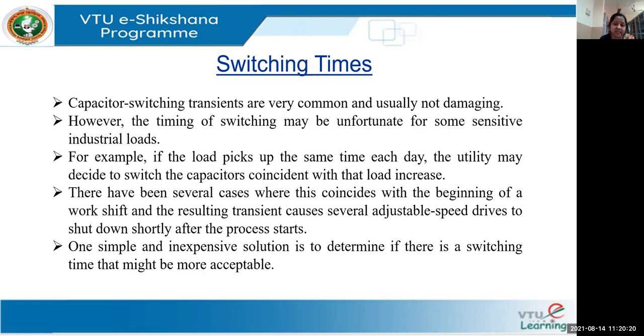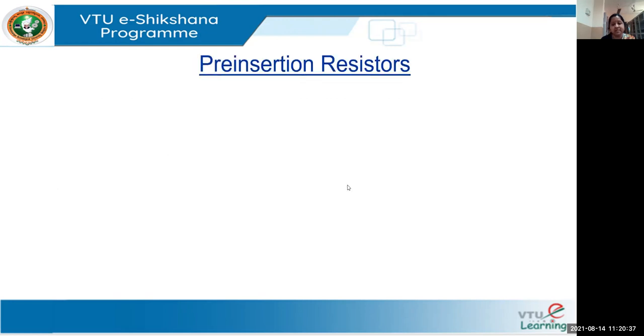Next we are going to see what factors or elements can be added to the system to avoid these transients. We can use pre-insertion resistors. The pre-insertion resistor will limit the high-frequency surge because the main problem is that when these surges happen, the first peak is very important to control. That can be done with the help of a resistor — that is what is meant by pre-insertion of a resistor.